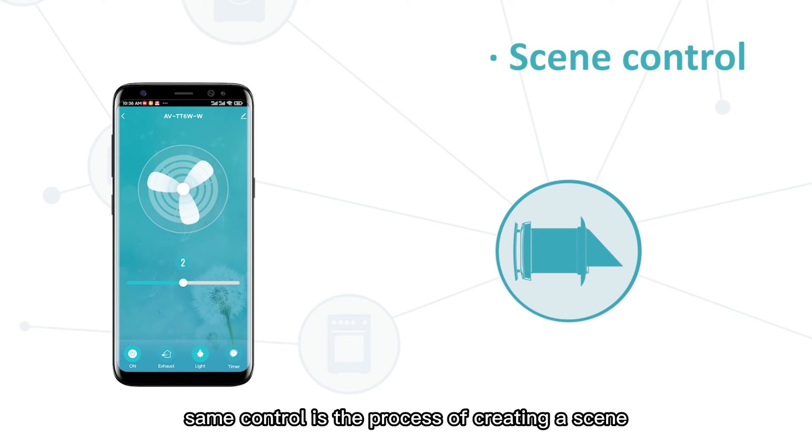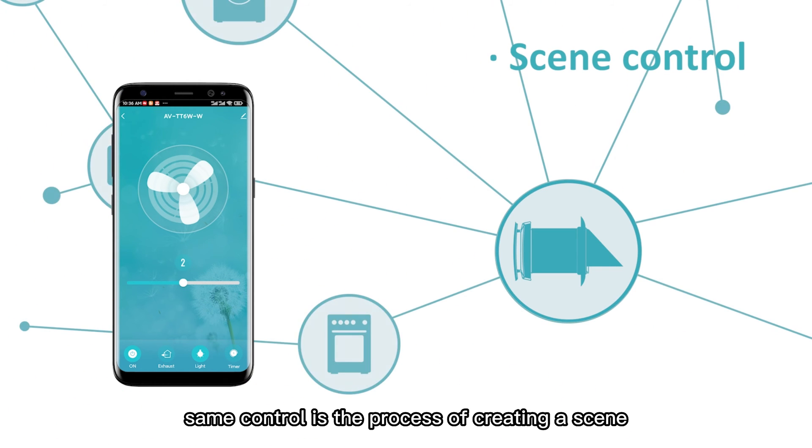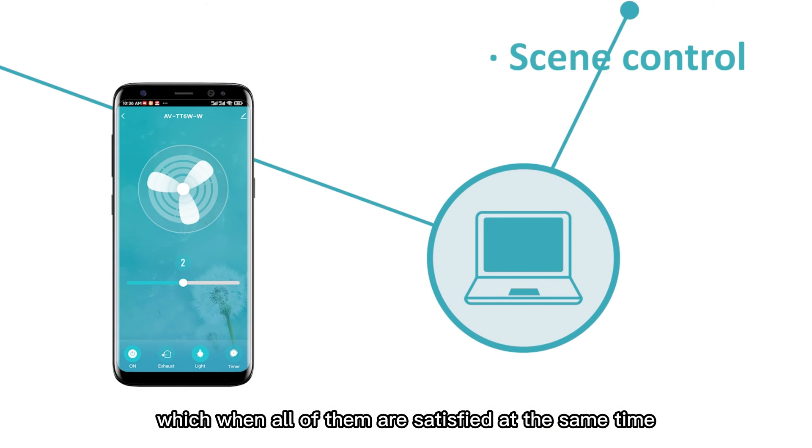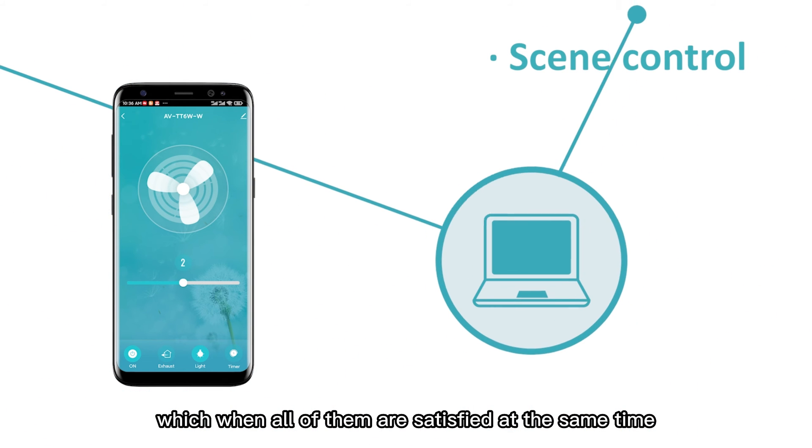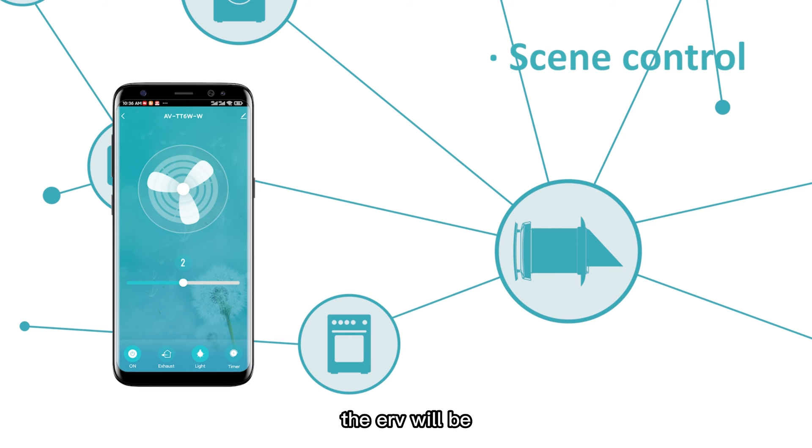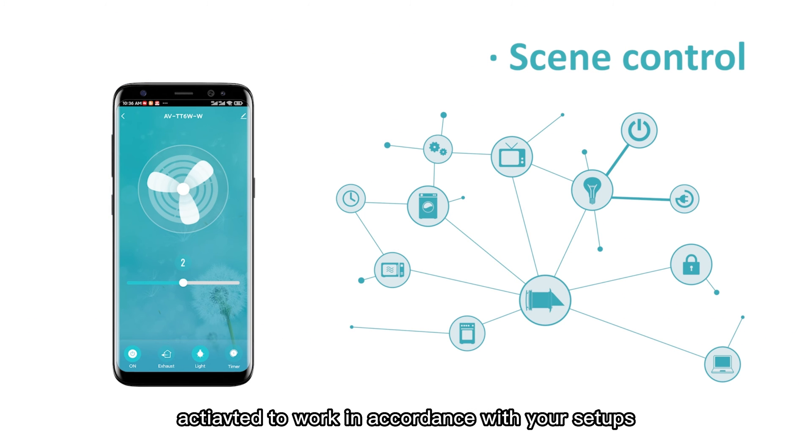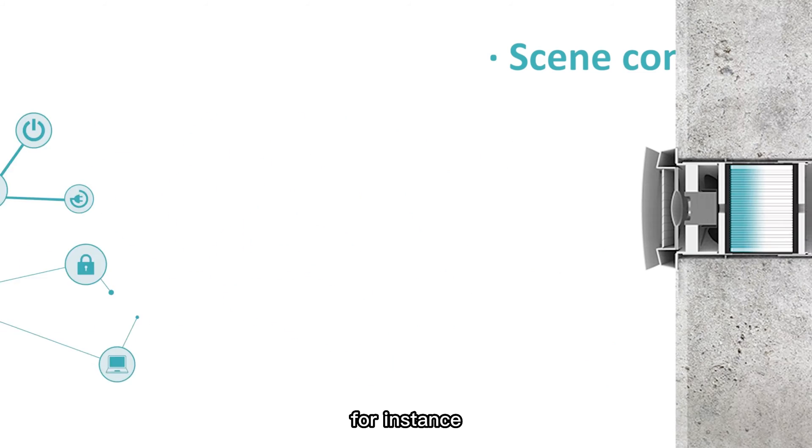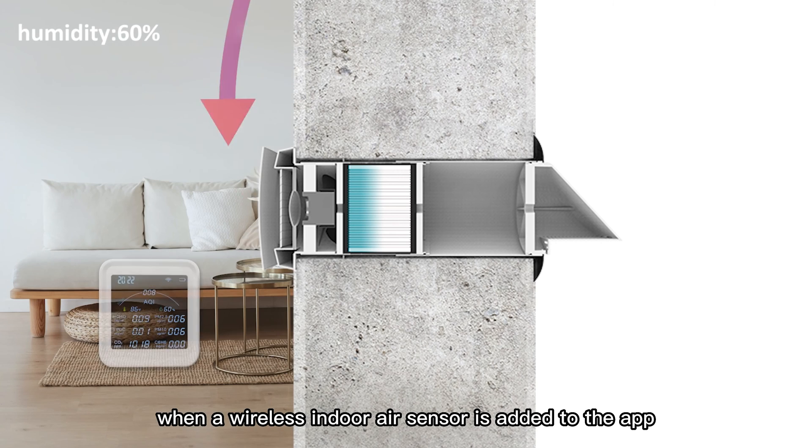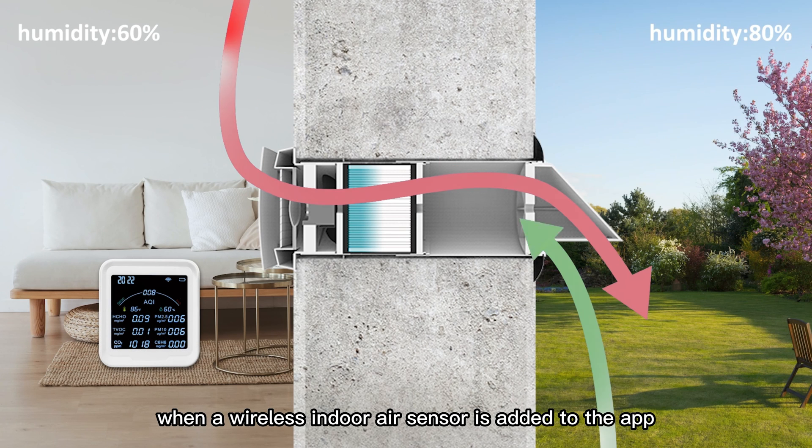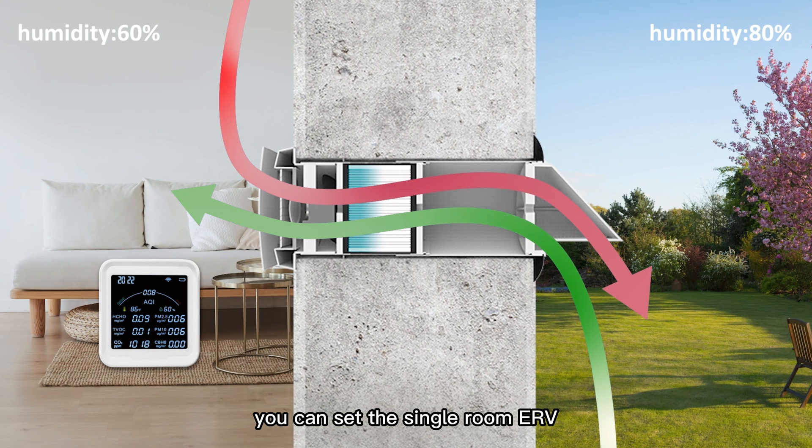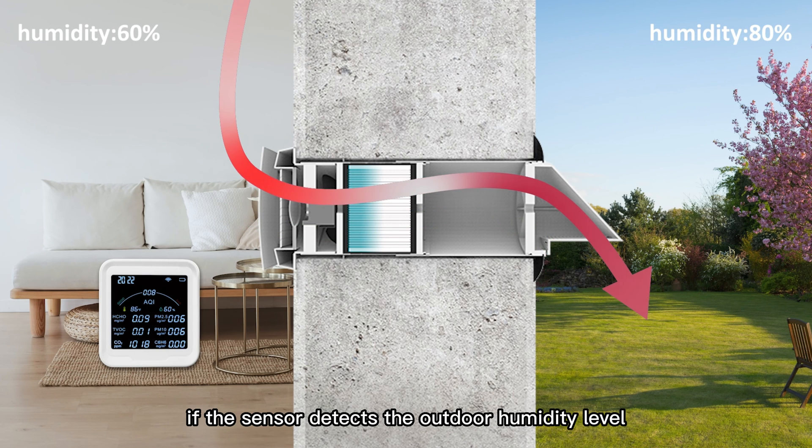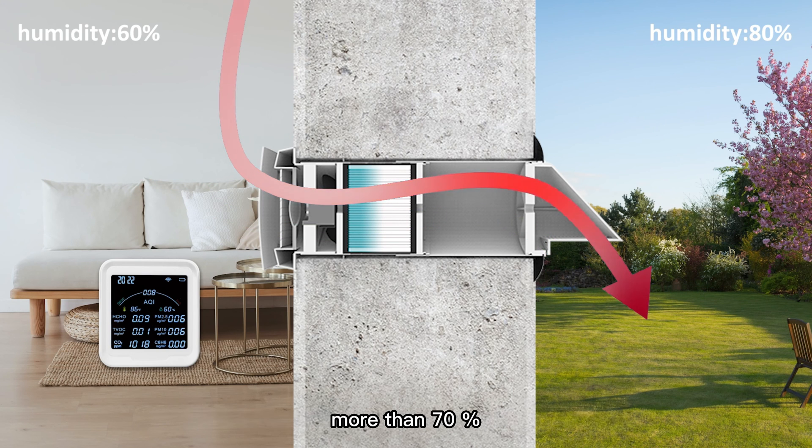Scene control is the process of creating a scene by setting up a number of requirements, which, when all of them are satisfied at the same time, the ERV will be activated to work in accordance with your setups. For instance, when a wireless indoor air sensor is added to the app, you can set the single room ERV to switch to extracting mode if the sensor detects the outdoor humidity level more than 70%.